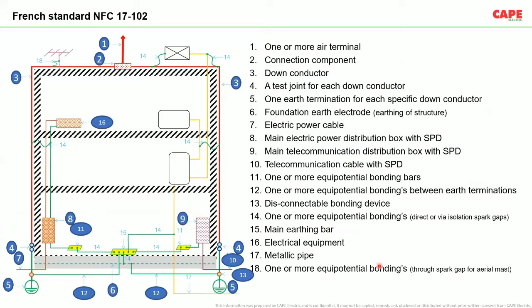For example, people claim that ESE rods are as per the French standard. Since I spoke about the French standard, I should also show this. The French standard is asking for perfect equipotential bonding, not only the ESE rod, but equipotential bonding. Whereas in our case in India, we use only the ESE rod and the rest of the items specified in the standards are not carried out. So please be sure that ESE we are not going to talk about.